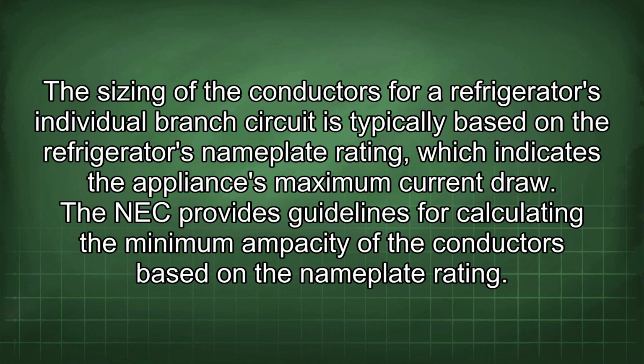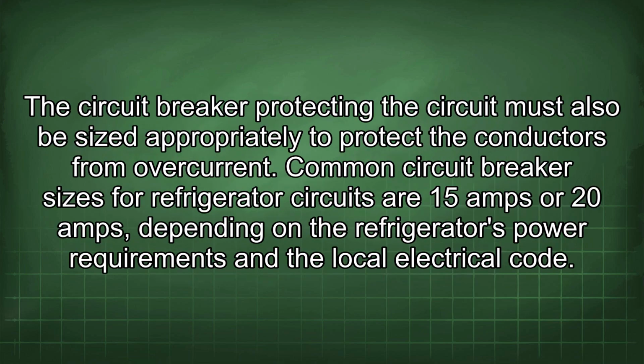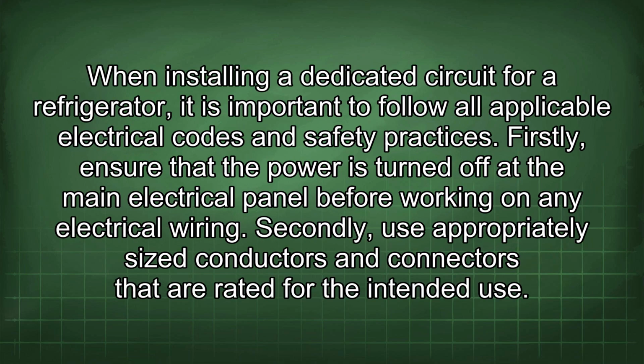The sizing of the conductors for a refrigerator's individual branch circuit is typically based on the refrigerator's nameplate rating, which indicates the appliance's maximum current draw. The NEC provides guidelines for calculating the minimum ampacity of the conductors based on the nameplate rating. The circuit breaker protecting the circuit must also be sized appropriately to protect the conductors from overcurrent. Common circuit breaker sizes for refrigerator circuits are 15 amps or 20 amps, depending on the refrigerator's power requirements and the local electrical code.